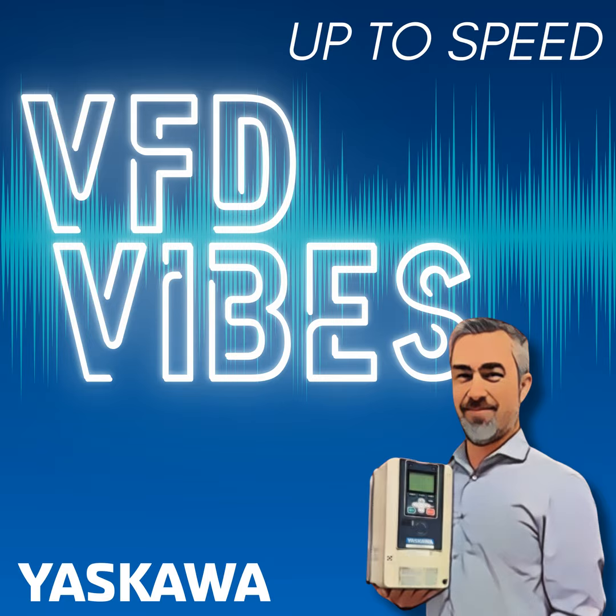Now, in these open delta systems, the imbalance is really bad. So there's a lot of 120 hertz ripple on the bus, and that ripple can be excessive. So Yaskawa came up with a patented system to detect this bus ripple and reduce the speed limit on the drive, the maximum frequency, so the drive actually slows down.